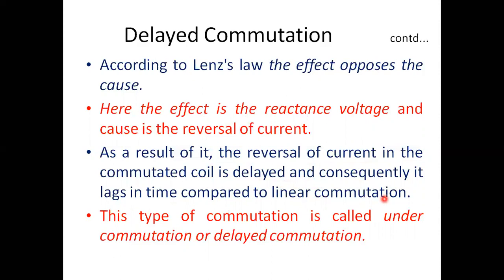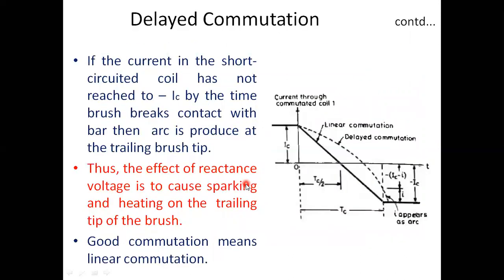This type of commutation is called under-commutation or delayed commutation. If the current in the short-circuited coil has not reached negative IC — the initial value in the reverse direction — by the end of the commutation period, there must be some sparking. This is not good for the brush or commutator segment. The actual linear commutation follows a straight line, while delayed commutation lags, and at the end of the commutation period there is still some current remaining, causing sparking.